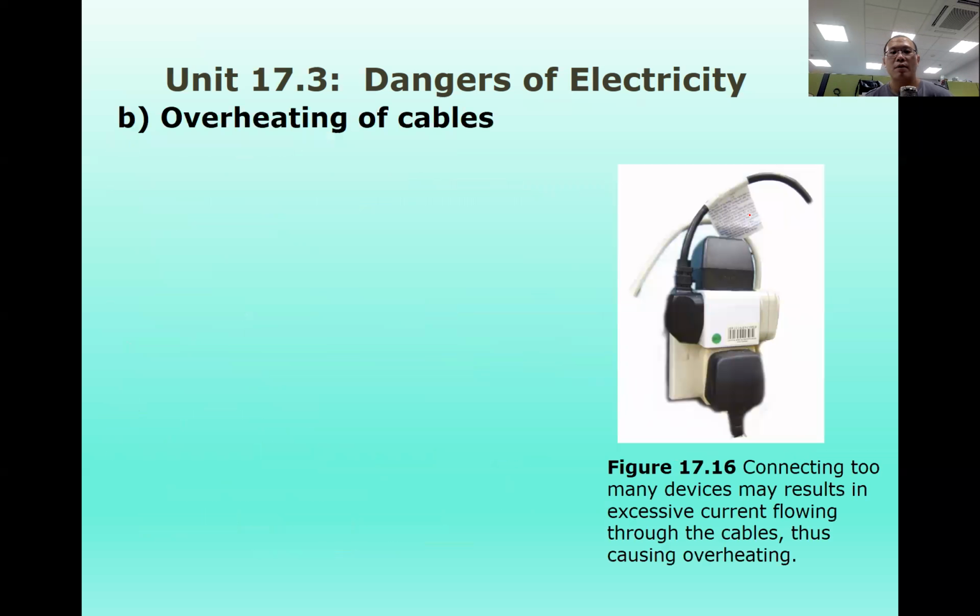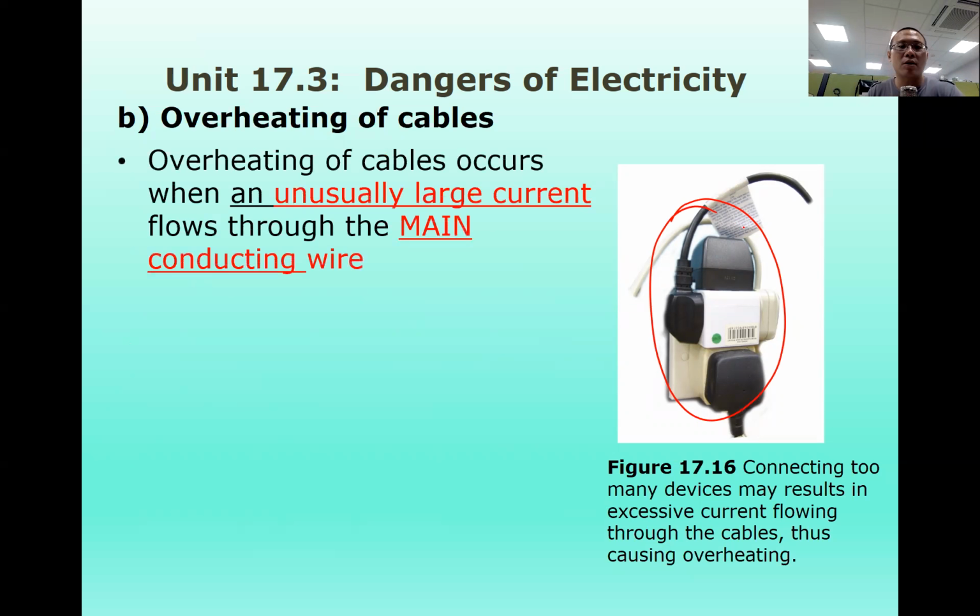Now, the other hazard we talk about is overheating of cables. One of the common examples, and one of the main causes, is this type of scenario: the use of a multi-plug, where you have multiple sockets attached to the plug itself. What's the problem with this? When you have multiple sockets drawing current from a single socket, you're drawing a high amount of current from the main conducting cable.